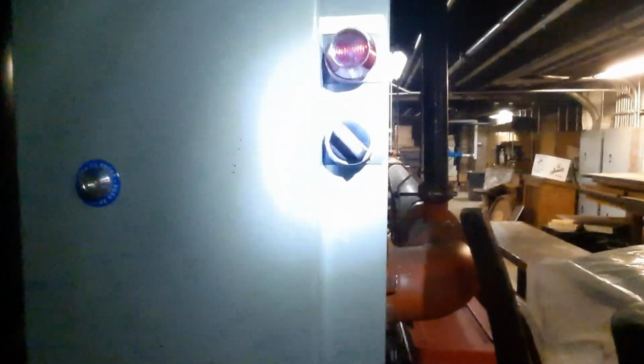You can see we got stuff everywhere, but these are our main circulating pumps. So these circulate water throughout the building, all five floors or so. We got starters inside of here. We have pump one and pump two. Sometimes you'll have a lead lag system that changes them automatically. I've got a tag here that says I changed over in 2020, so basically we don't run an auto. We just set them in hand, and I'll flip these over every year or so just to give the pump a break and let the other pump run.